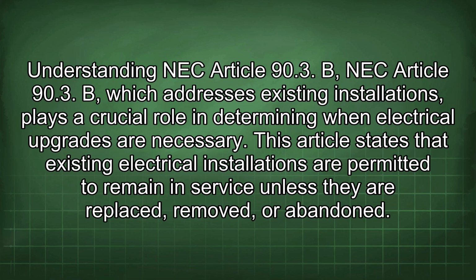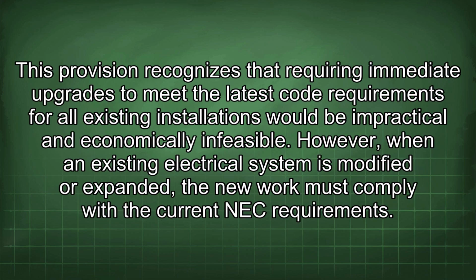Understanding NEC Article 90.3. The NEC Article 90.3(B), which addresses existing installations, plays a crucial role in determining when electrical upgrades are necessary. This article states that existing electrical installations are permitted to remain in service unless they are replaced, removed, or abandoned.